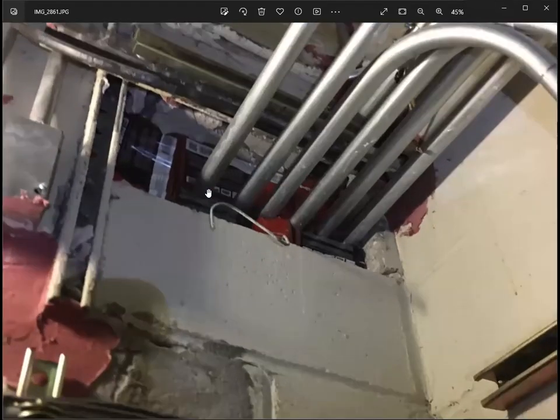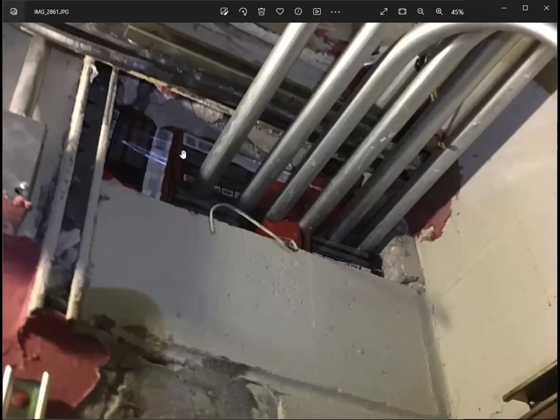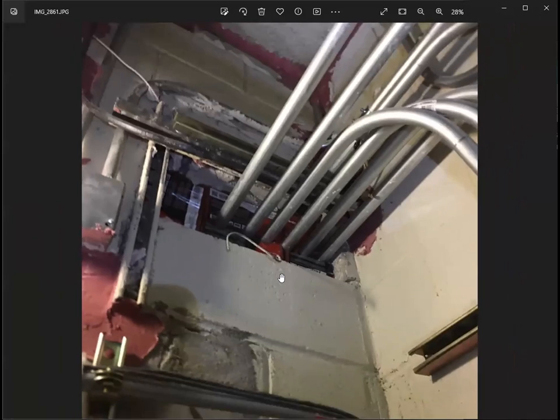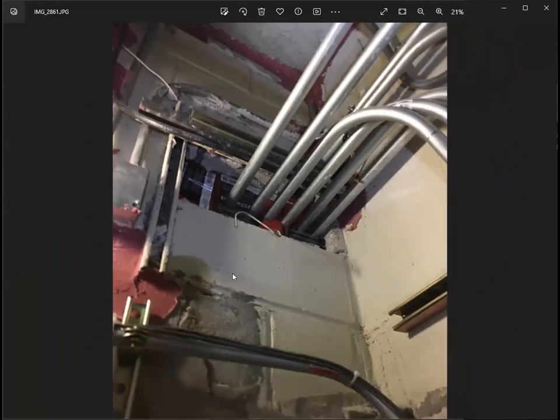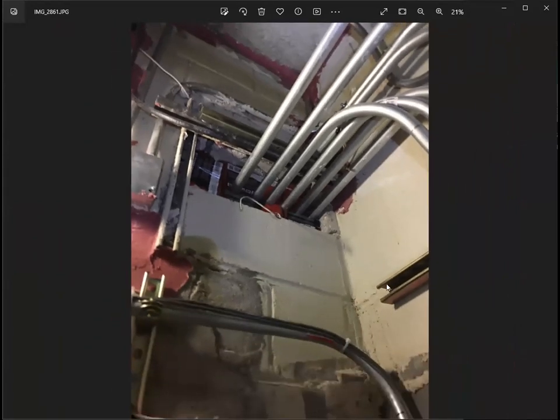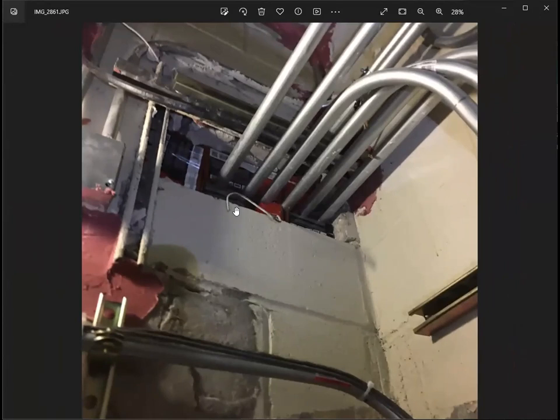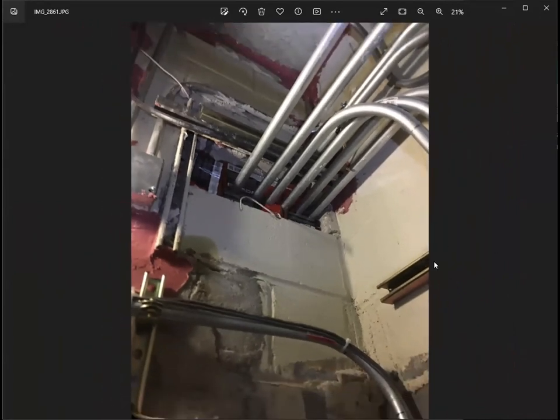So you need to check this material to see if it is rated for 2 hours or 3, and you need to look on the existing drawing, because this is an existing wall. If you're not so sure, put it in the report and address it to the engineer of record so that they can address how to correct it, or probably accept it as it is. You need to attach this photo when you're doing your inspection report.